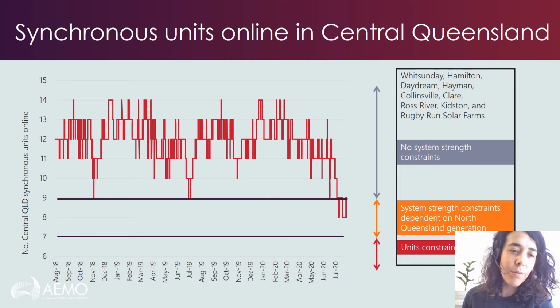This chart shows the importance, in our view, of planning for how synchronous generators are connecting to and dispatching in the NEM. You can see here that since August 2018, we had certain numbers of synchronous units online in central Queensland typically. This is their typical online bidding and dispatch pattern in the NEM. And you can see that towards the middle of 2020, we had fewer units available, and consequent system strength constraints being brought in Queensland to manage the impact of that change. This slide is just designed to show the importance of us anticipating or understanding where different units will be performing and dispatching in the NEM.